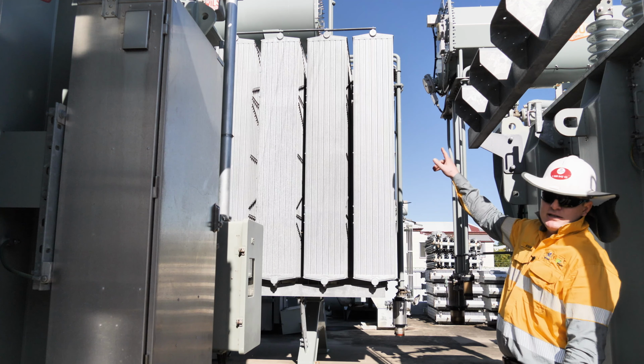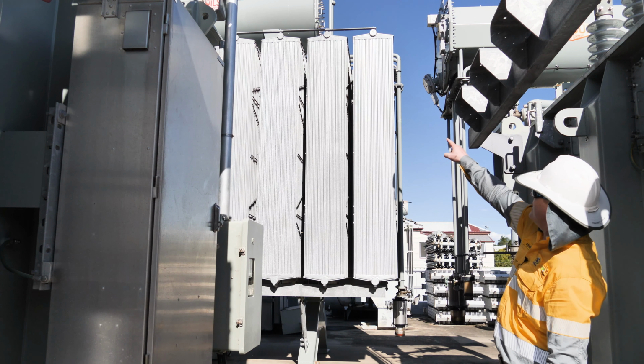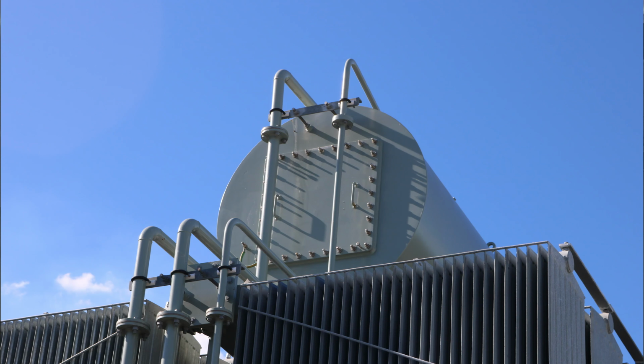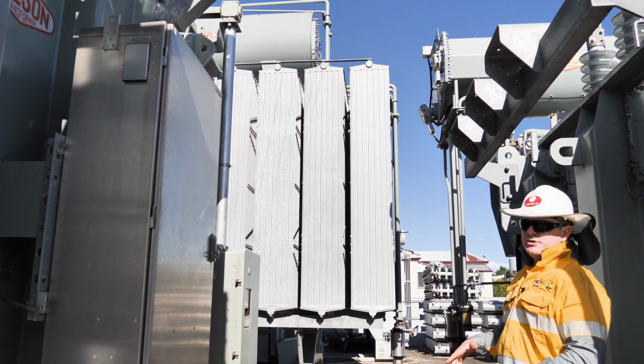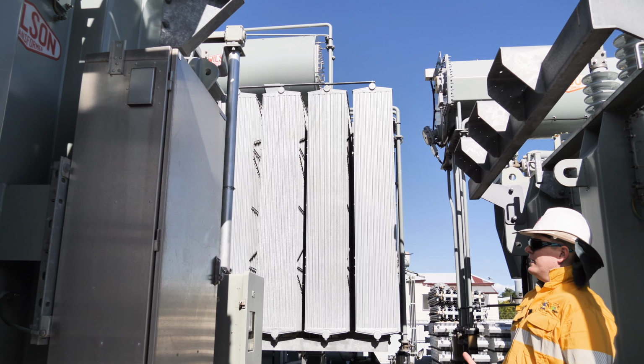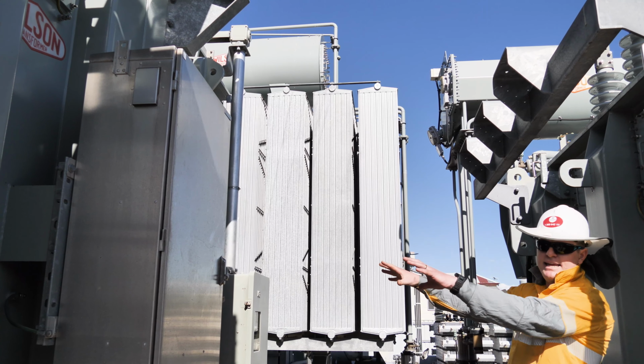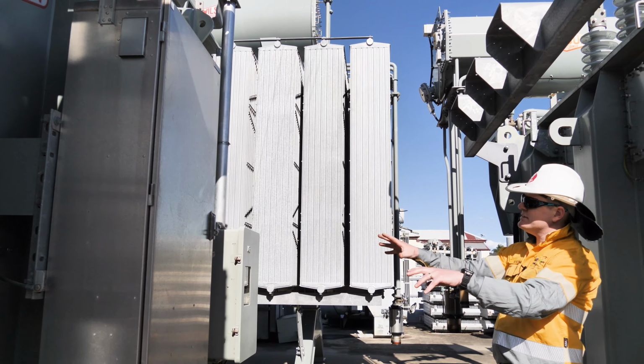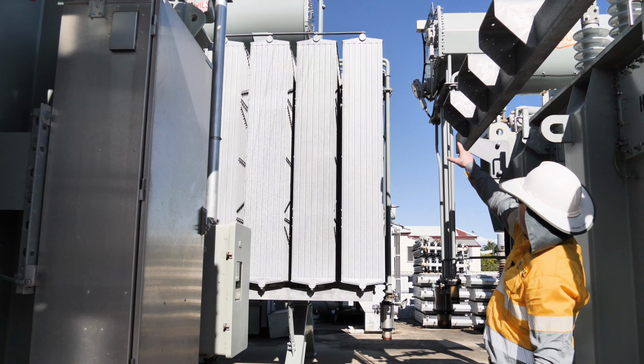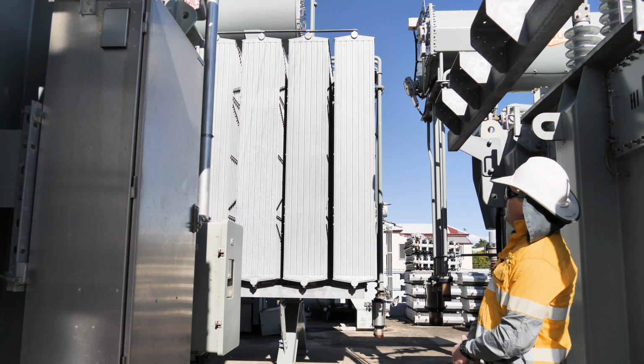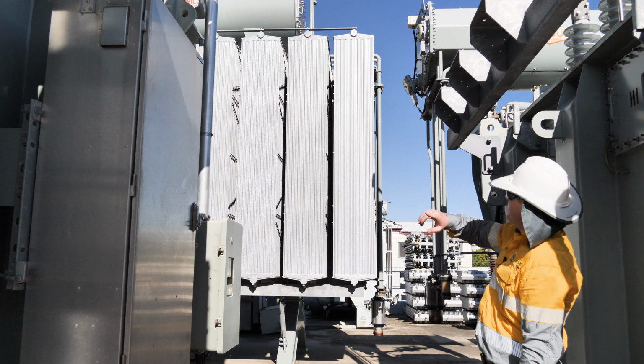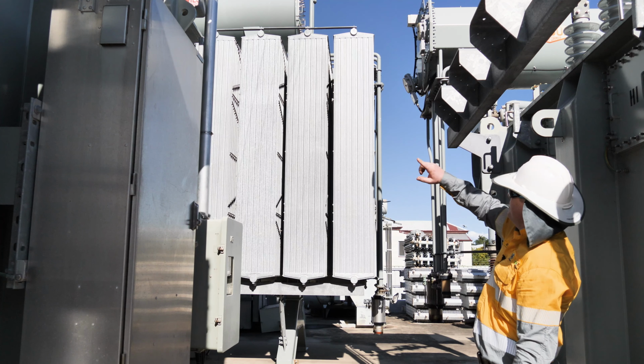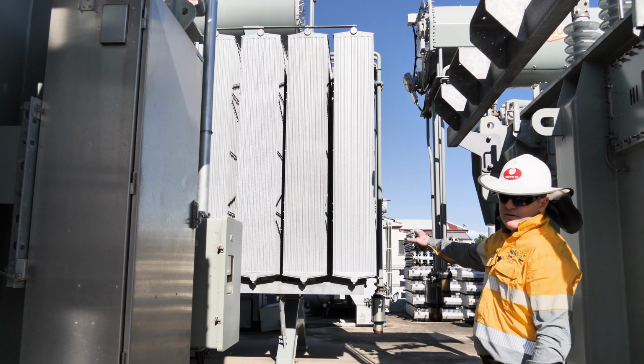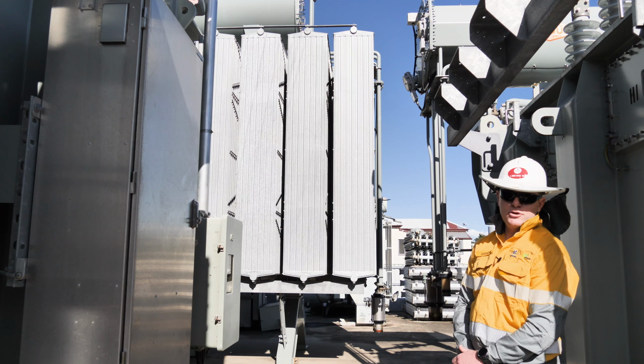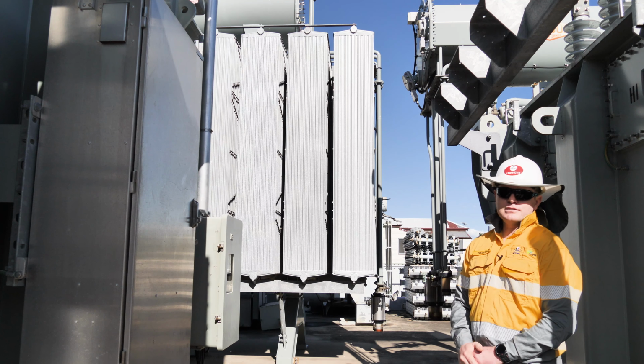The other key feature on this transformer is that big tank up there that says Wilson transformer. That is called the conservator. The oil in the transformer, the total amount of oil, is made up of oil that sits in the main tank itself, this big box, as well as the oil in that conservator. Any of the hot oil will move into that conservator before running down through the radiator fins to be cooled and pumped back into the transformer.